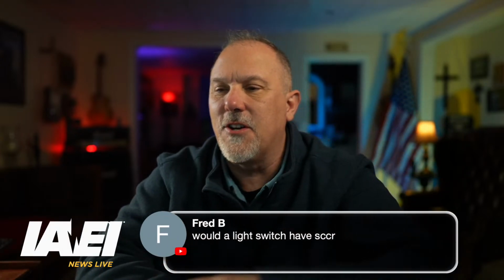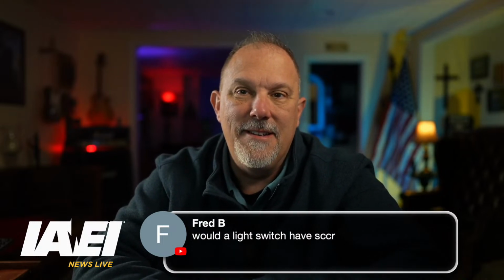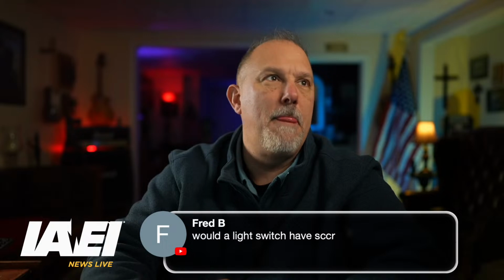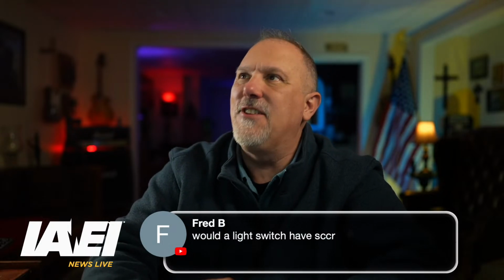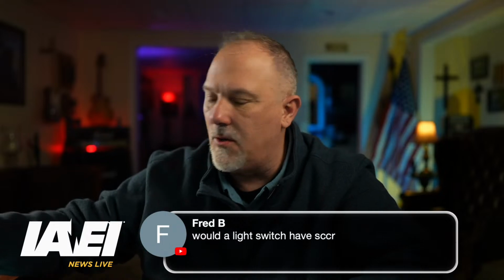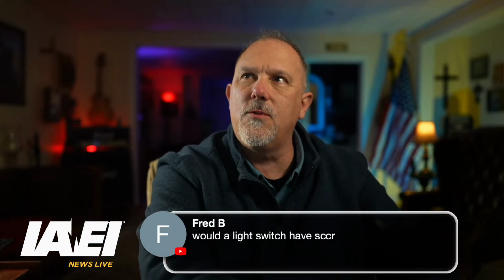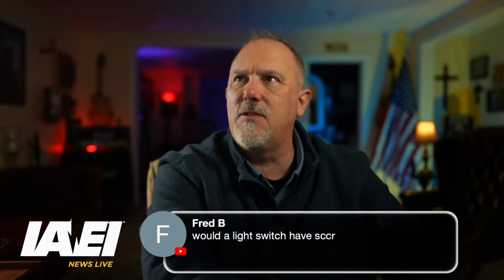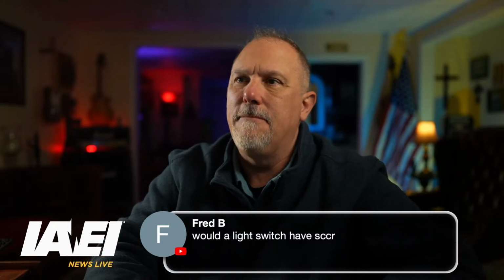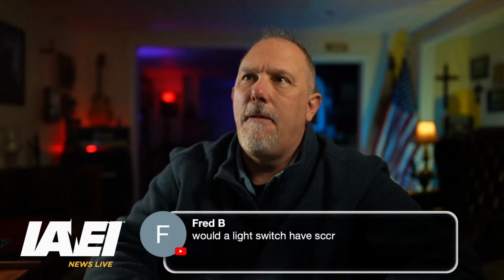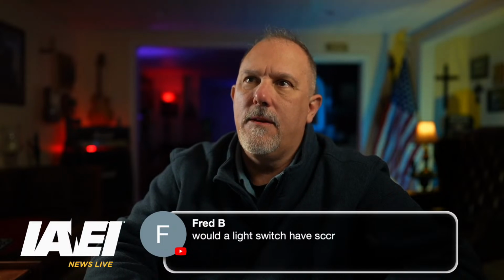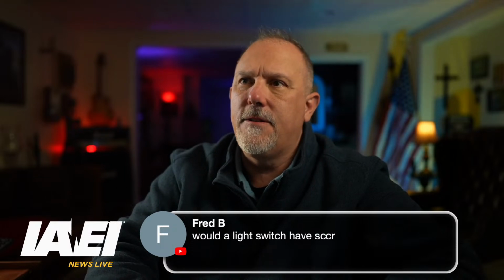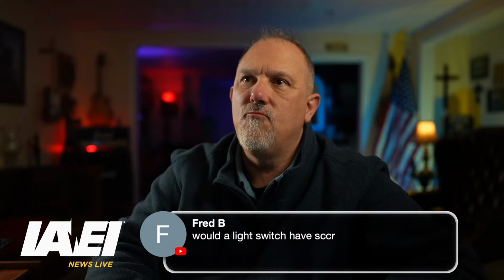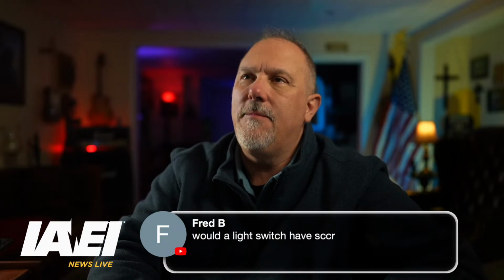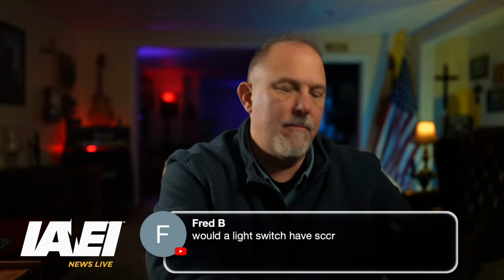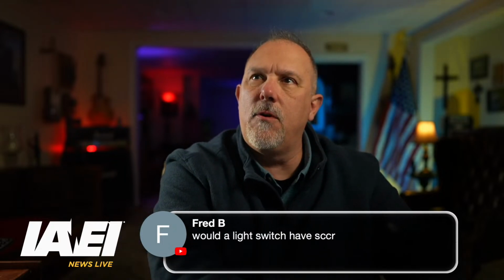Would a light switch have a short circuit current rating? Absolutely, it does. It's funny, you know what's really interesting is even a receptacle, short SCCR of a light switch. I'm going to see what we can find. What is the short circuit current rating of a... You know what I'm going to do is I'm going to go and find... we'll do Pass and Seymour.